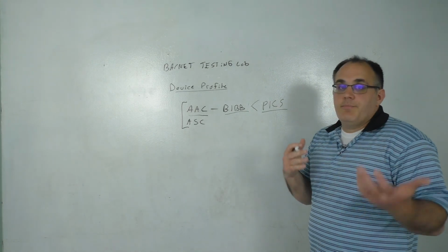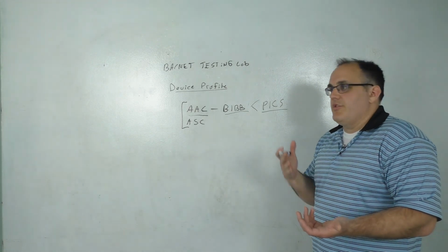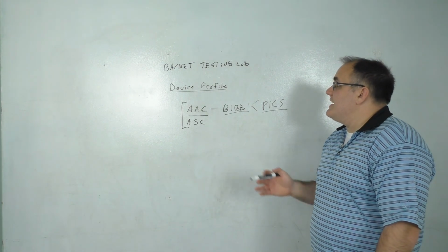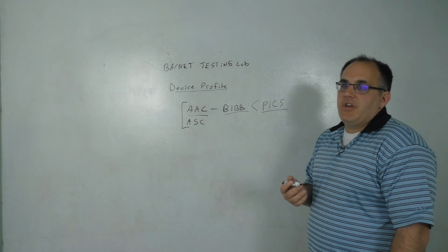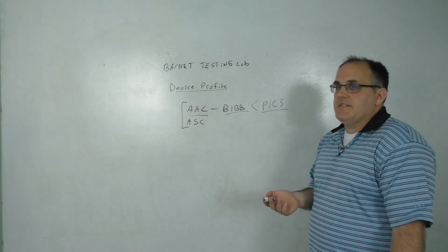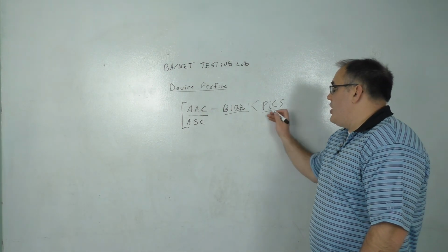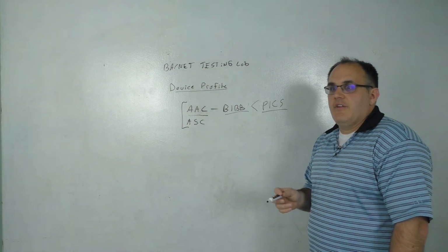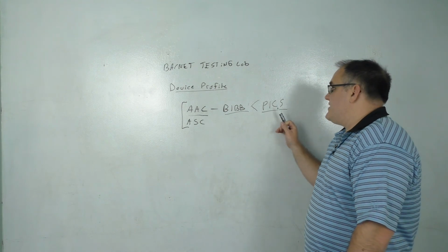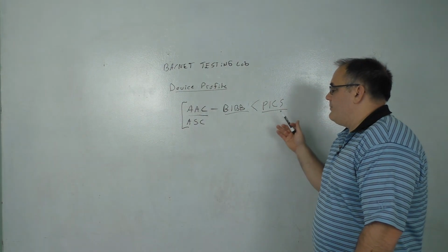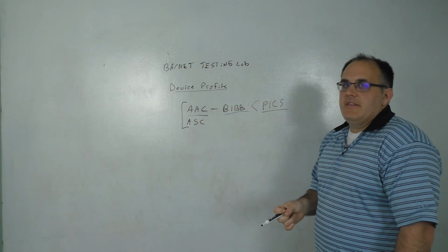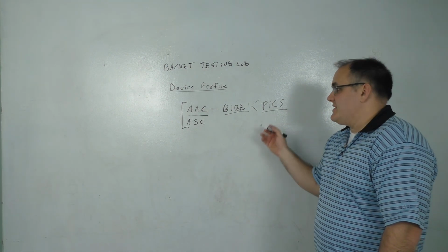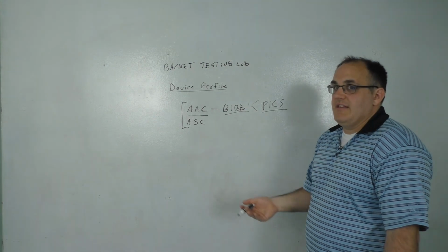So then as a building automation professional, whether you're in sales, engineering, or a technician, if you are told, hey, we're putting a BACnet IP card on this piece of equipment, you can actually go and see if it has a PIC statement. That should be kind of a red flag right there. If you're buying a bunch of rooftops and they have BACnet cards and they aren't compliant to any profile, that's kind of scary. That would be something you would want to be concerned about, because that means that they haven't tested it for interoperability.